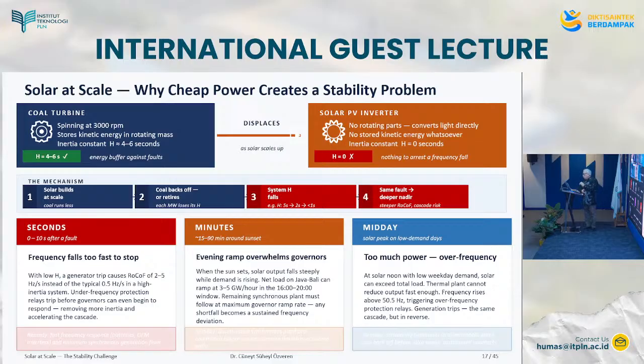What we have now is coal turbines, right? And we want to replace them with solar PV inverters. Coal turbines spin at about 3,000 RPM. They store kinetic energy in the rotating mass, and the inertia constant is about 4 to 6 seconds. Between 4 and 6 seconds.